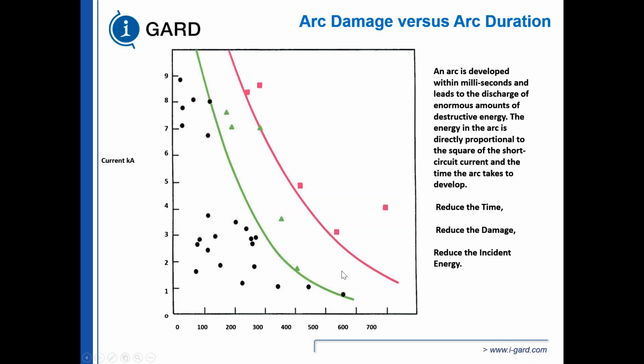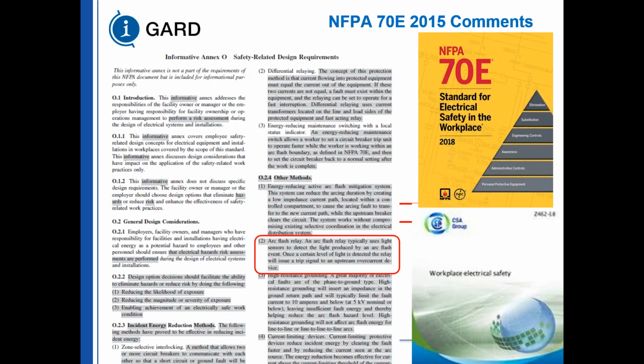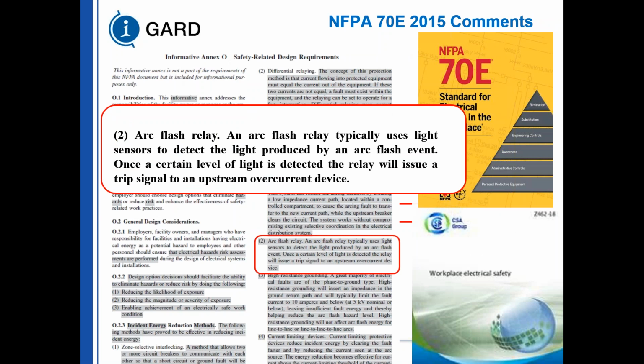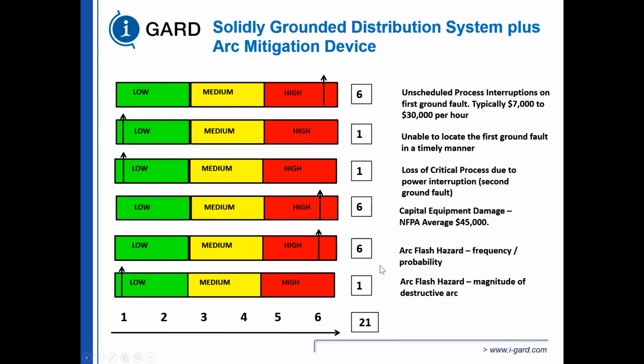For only 600 milliseconds and 3.5 kA of arcing current is enough to burn through the steel of an enclosure. So you can imagine in a solidly grounded system how much destructive current there is. You could put in an arc flash sensor, and if you put in an arc flash sensor, you're going to detect the presence of the flash quickly in a solidly grounded system, and you're going to isolate much more quickly. But all we're basically going to do is lower the magnitude of destructive current. We're not going to lower the probability or the frequency of the flash hazard, and everything else stays the same.